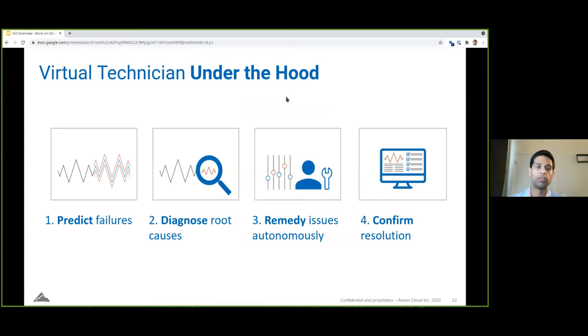Broad overview is first predicting failures and recognizing set point changes. This happens all the time. A technician, and I'm not necessarily saying that this is wrong, but the technicians will go in, they're stressed out, they have to get to a bunch of jobs. They change a set point that should not be changed. They say, oh, this case is actually struggling to keep food cold, so they'll just bury the set point, which means they'll just put it really, really low.